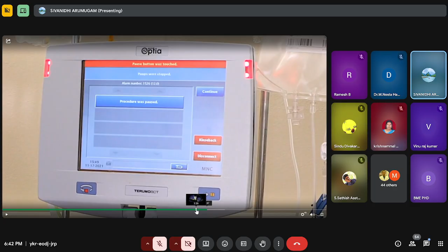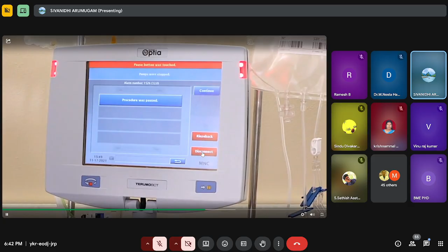The Spectra Optia's automated interface. These are for different protocols. I don't want to confuse you all. This one I told you, right? If, for example, AC is not passing through the detector, we will get a beep sound with a red light, and the screen will show a red status line. It will show what has happened. In this case, the operator pressed the pause button. So it's a safety alarm. Safety is very important here.